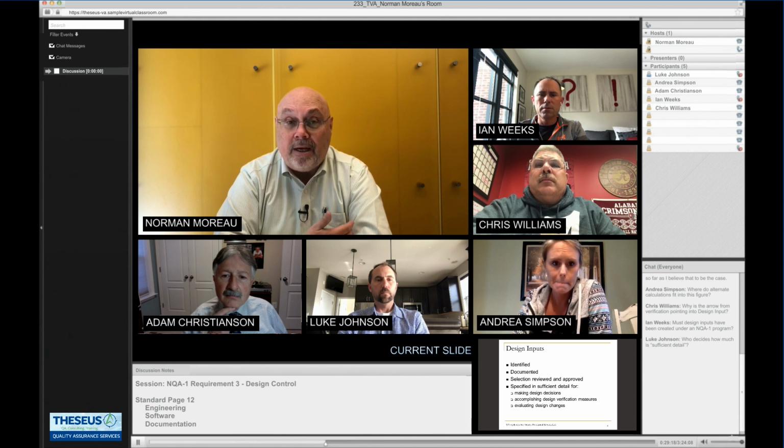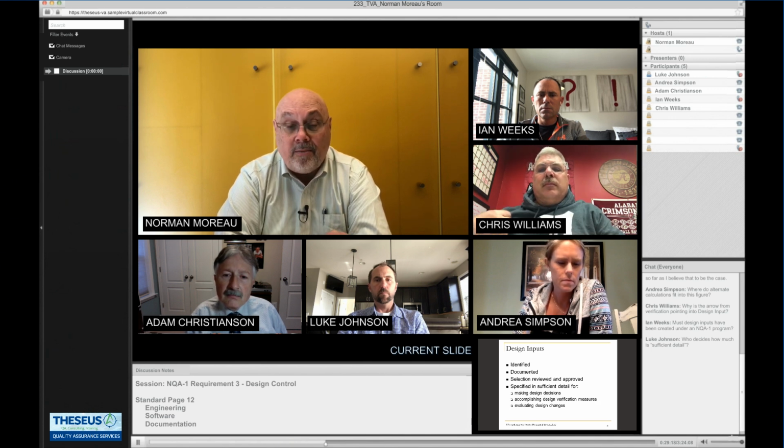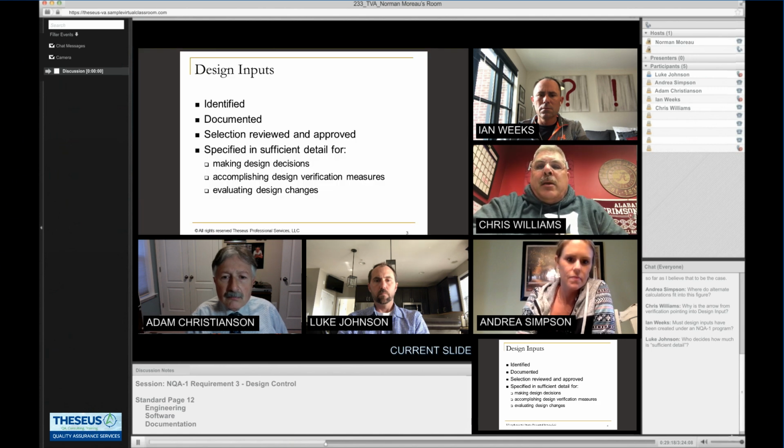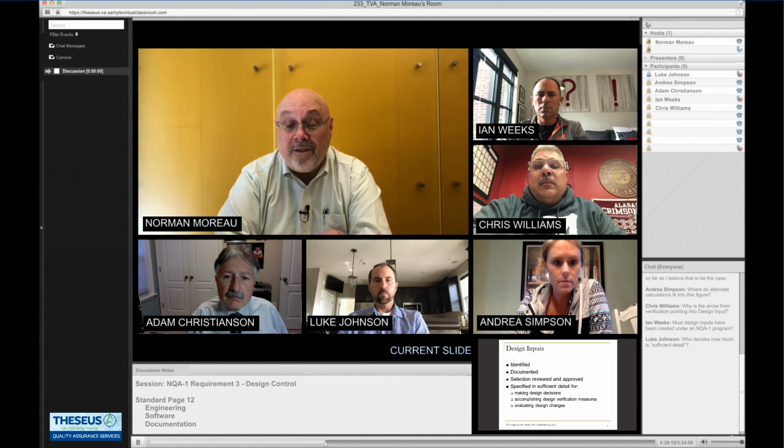so that somebody can actually do a verification, because everything we do has to be verified and has to be done by somebody who didn't do the work. And then the last item is it's used in evaluating design changes 5-10 years down the road. Some of these plants are running 40 years. I've got to know what you did as far as making your decision.